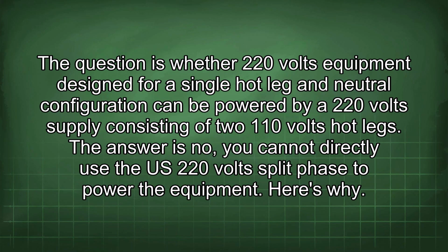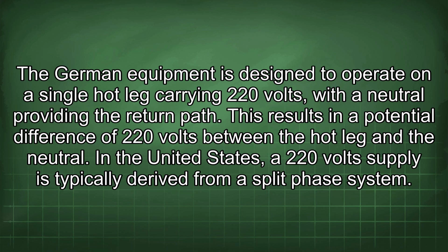The question is whether 220 volt equipment designed for a single hot leg and neutral configuration can be powered by a 220 volt supply consisting of two 110 volt hot legs. The answer is no, you cannot directly use the US 220 volt split phase to power the equipment. Here is why. The German equipment is designed to operate on a single hot leg carrying 220 volts, with a neutral providing the return path. This results in a potential difference of 220 volts between the hot leg and the neutral.